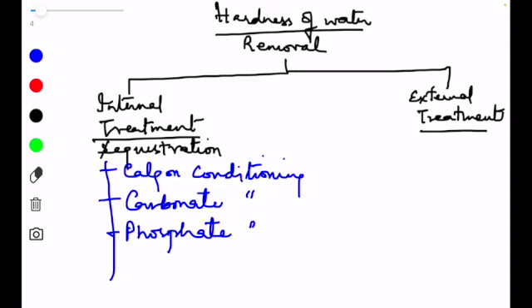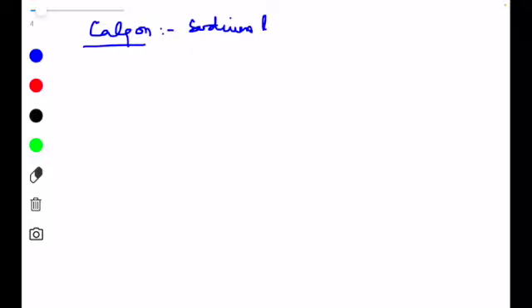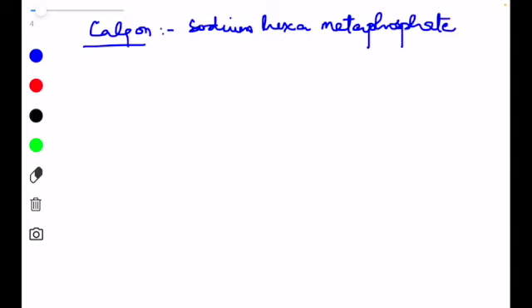In calgon conditioning, a chemical compound commercially called calgon is used. Chemically it is sodium hexametaphosphate. This calgon is added to the boiler water to prevent the formation of scale and sludge. Calgon converts the scale-forming impurity — which is calcium sulfate — into a soluble complex compound.